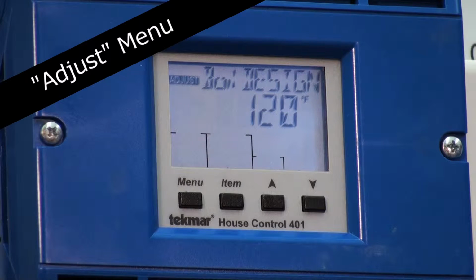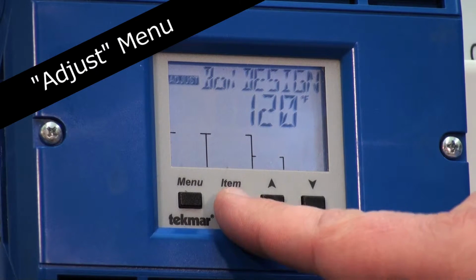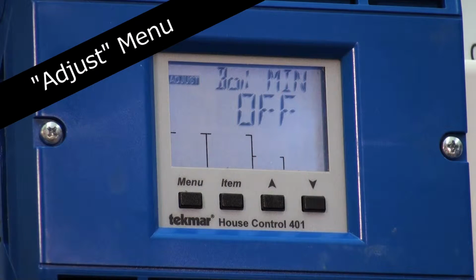Boiler design. This is the water temperature at what we are going to be at the -15 if that's your design point outside. So -15, we're targeting 120. That's your setting here. The boiler minimum, in this case being a ModCon boiler, it is off. We don't care about the return water temperature. The colder the better. Cast iron boiler, you might set that to a minimum of 140 to protect the boiler.